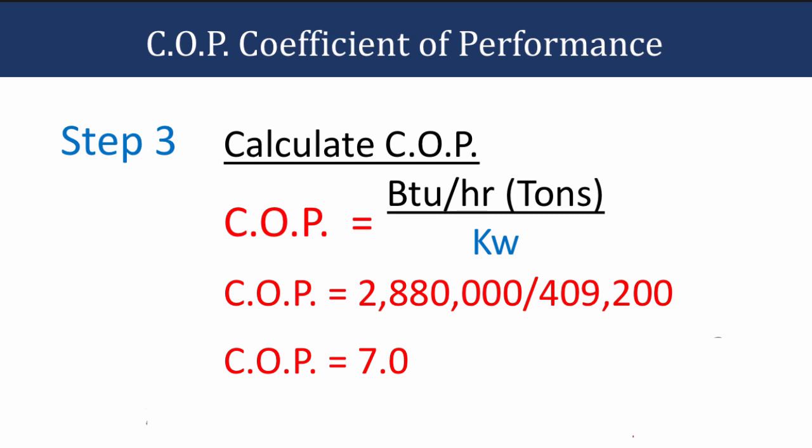The calculation is simple. We take the output on top — 2,880,000 BTUs per hour — divided by the input 409,200 BTUs per hour, and it gives us a COP of 7. We'll explain what this number means, whether that's good or bad, in the next few slides.